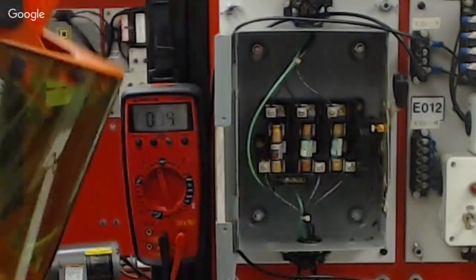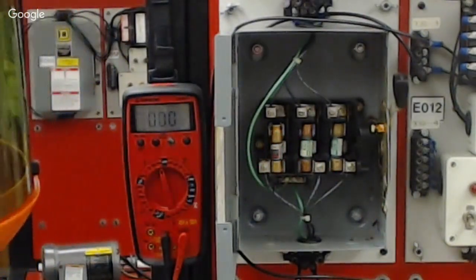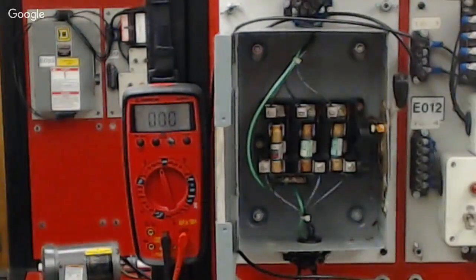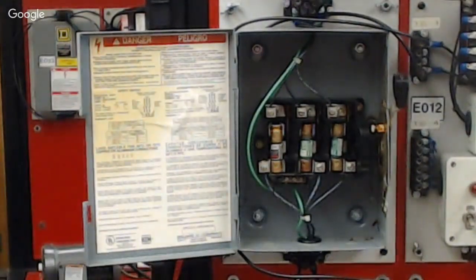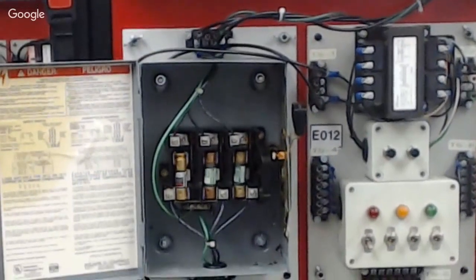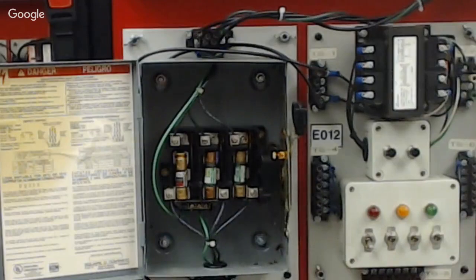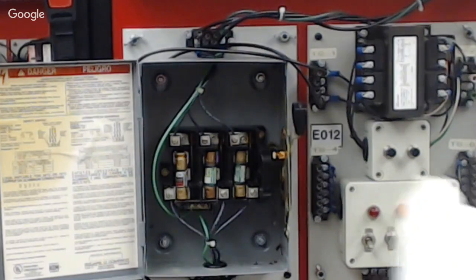Here's the problem. If you don't watch it, what you will do is you will actually read through the control transformer. So here we have the control transformer hooked up, and the current is actually coming off L2, going all the way back through the coil and coming back to the bottom side of L3. So when I checked it to ground, I'm actually reading the voltage coming off L2 with the disconnect on. So you have to be careful of that backfeeding through the circuit.